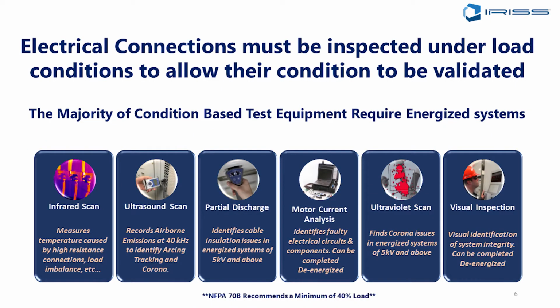But for the most part, to get really good asset health data, we need to have those assets energized and running under what we would call a normal level of load. All right, and NETA has some guidelines about what normal is, and for how long that asset should have been running before we try to take the data. So if we're doing infrared, for instance, we need to have had that asset running for a certain period of time so it's reached thermal stability, that things have had a chance to warm up as they would under normal conditions. So what are the technologies?